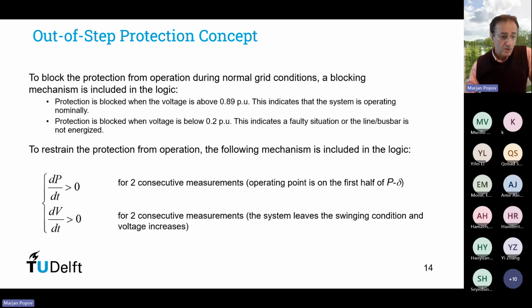The protection also makes use of restraining criteria. So these restraining criteria are also two. The derivative of the power is positive, and the derivative of the voltage is also positive for 2 consecutive measurements. The first criterion indicates that the operating point is on the first half of the power angle curve. And the second criterion indicates that the system leaves the swinging condition, so actually stabilizes and the voltage increases.